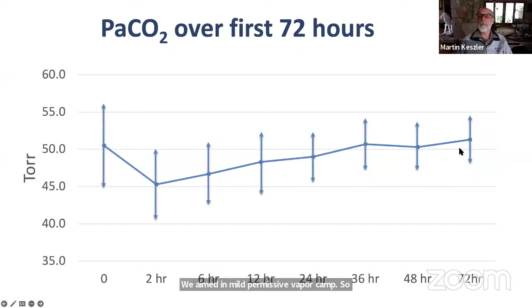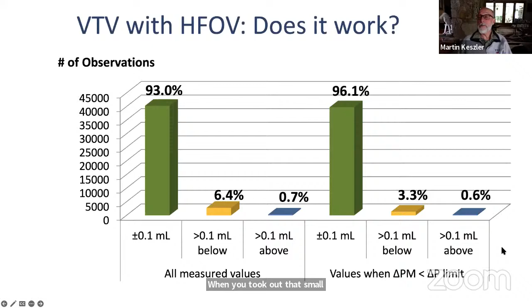And importantly, the measured tidal volume compared to the set tidal volume was within plus or minus 0.1 ml per kilo overall. And in a subset of babies, the tidal volume was more than 0.1 ml below, because the clinicians failed to adjust the pressure and the amplitude limit. So not allowing the ventilator to do what it was trying to do. When you took out that small proportion, it was even closer to 96%. So this device clearly did work very well, because it was managed by the bedside team who had no prior experience with the device. Despite that, there were no significant issues, no safety concerns.